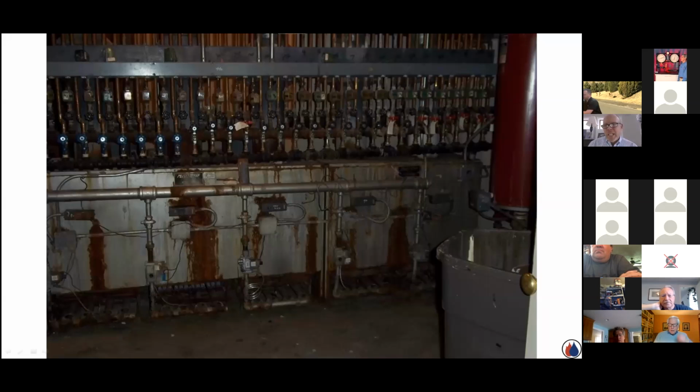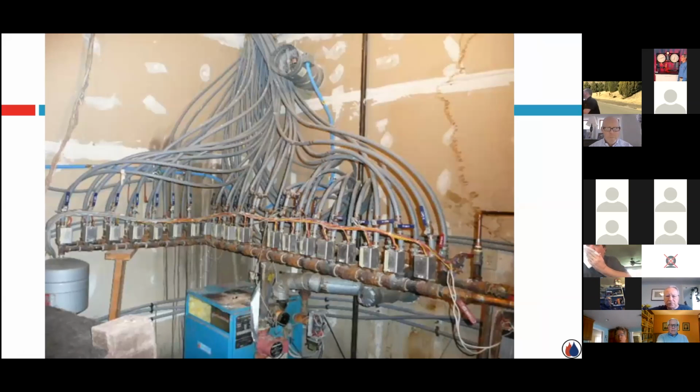And then off to the side here, you see the old famous Everhot sidearm heaters for domestic hot water, which would mean that these boilers stayed hot 24/7, 365 to be able to support any kind of domestic call, because it was instantaneous. So not up to your high efficiency standards, so to speak. But anyways, again, it's just some of the stuff you see out in the field. It's amazing. This always caught my attention.